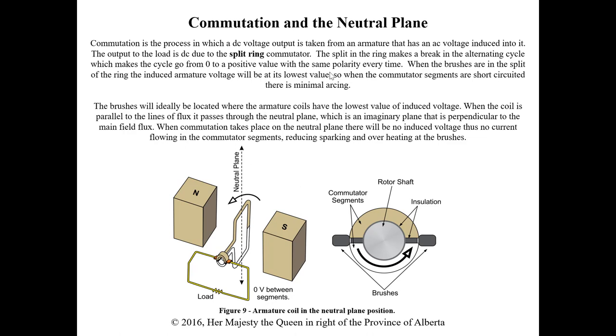Split rings are essential — they're the whole reason we get pulsating DC out of a full 360-degree rotating armature. When the brushes are in the split of the ring, the induced armature voltage is at its lowest value, so when the commutator segments are shorted there is minimal arcing. If contact were made at peak voltage, we'd have an extreme amount of arcing at the expense of our brushes. The brushes ideally are located where there is the lowest value of induced voltage — when the coil is parallel to the lines of flux, passing through the neutral plane.